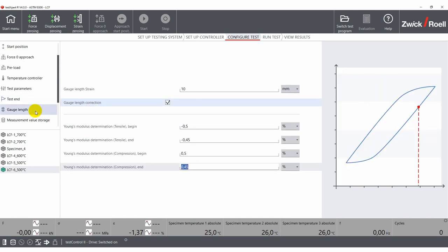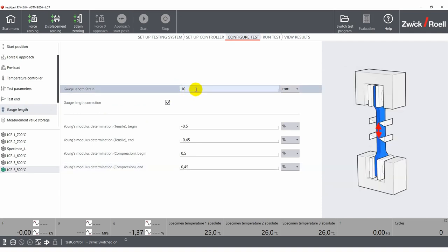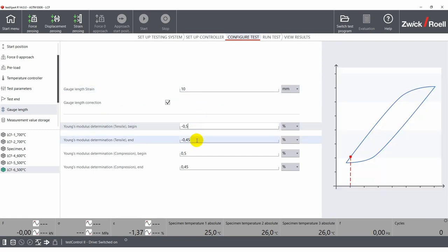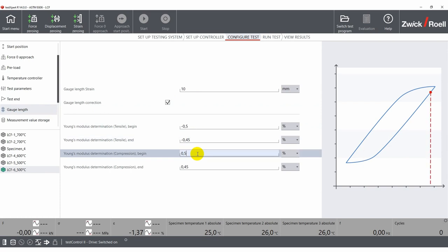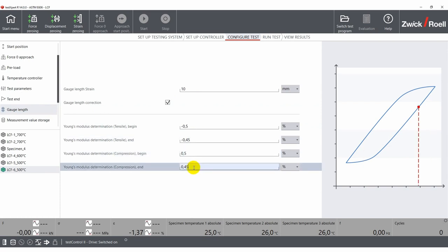Under gauge length, you can define the gauge length of the extensometer. Since the ASTM E606 standard also determines the Young's modulus in both the tensile and compression direction, you can set the starting and end points for that determination.